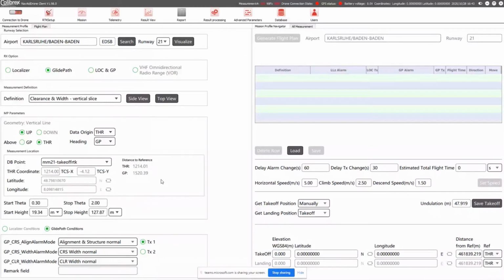Then all measurements will be performed at this location for the vertical. Automatically we have the distance to the threshold, the distance to the glide path, and based on those distances, the automatic start and stop heights are calculated. We use as a parameter theta, which is the multiplier of the glide path angle. Again, everything is related to the database, so typically in that case our glide path angle in the database should be 3 degrees, meaning we want the measurement from 0.9 to 6 degrees.